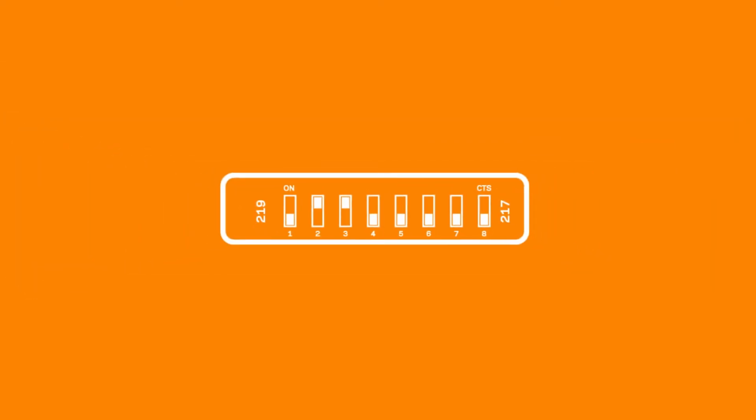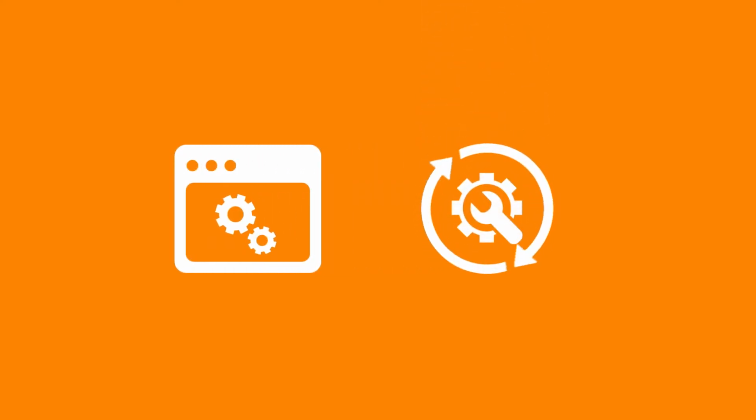Note here, if DIP switch 2 and 3 are not turned off, the controller address will need to be configured multiple times during the upgrade, as it drops its IP configuration settings upon restart.